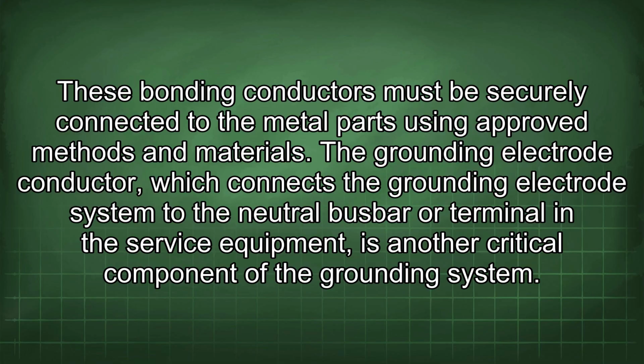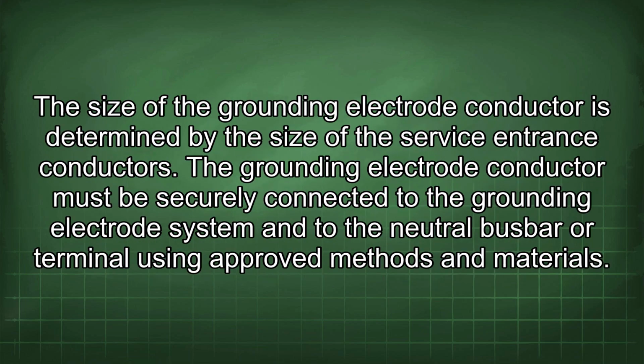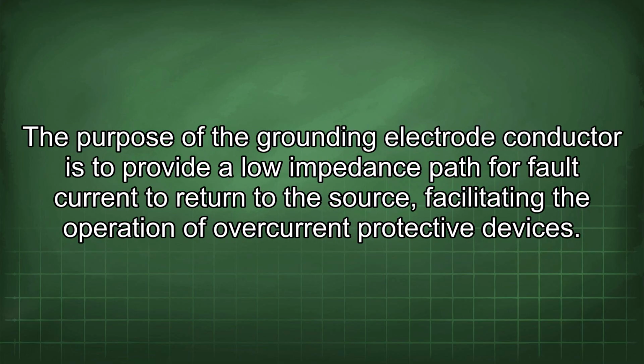The grounding electrode conductor, which connects the grounding electrode system to the neutral busbar or terminal in the service equipment, is another critical component of the grounding system. The size of the grounding electrode conductor is determined by the size of the service entrance conductors. The grounding electrode conductor must be securely connected to the grounding electrode system and to the neutral busbar or terminal using approved methods and materials. The purpose of the grounding electrode conductor is to provide a low impedance path for fault current to return to the source, facilitating the operation of overcurrent protective devices.